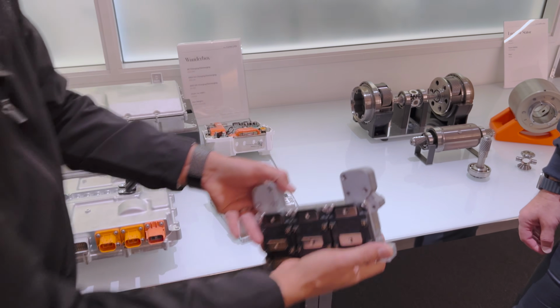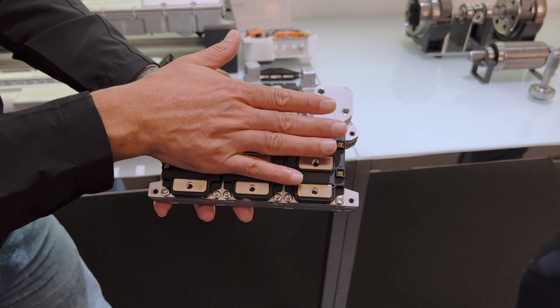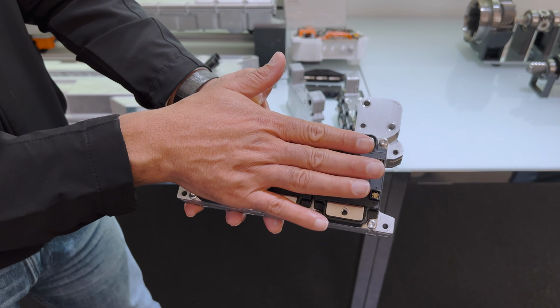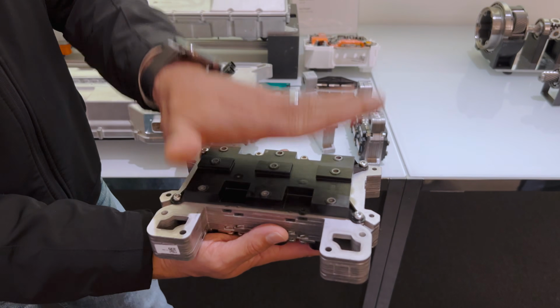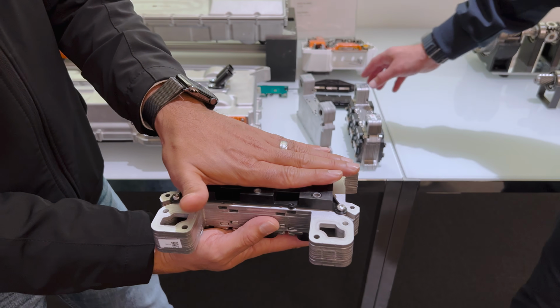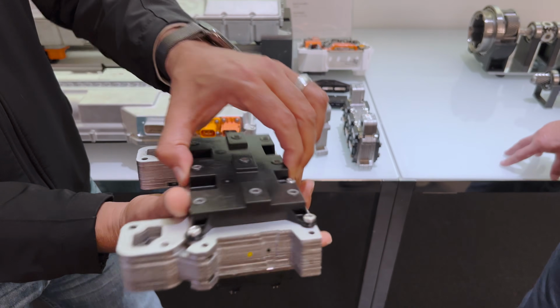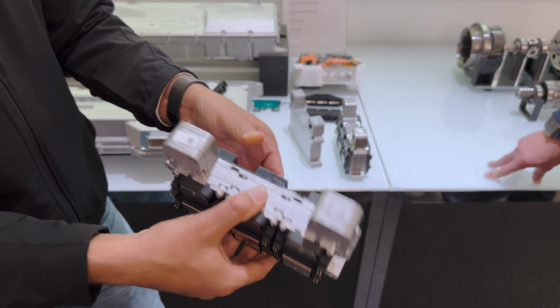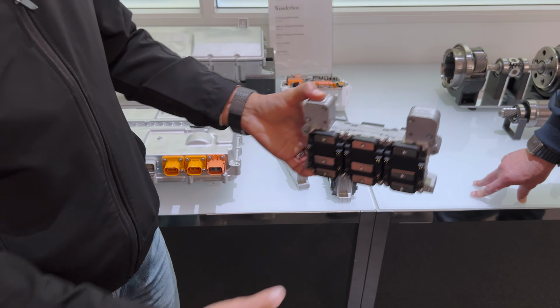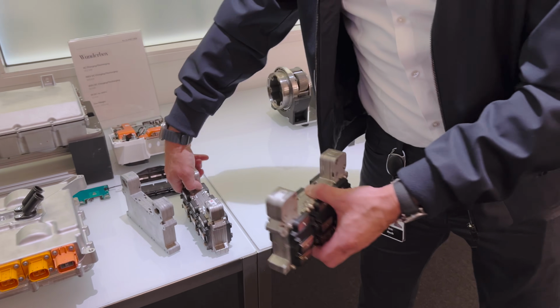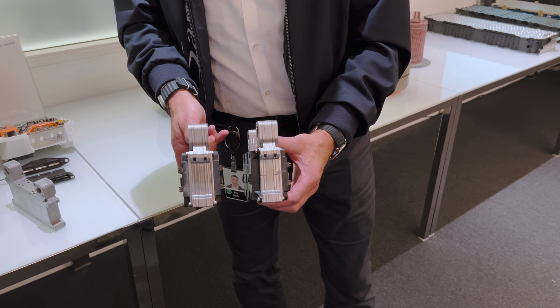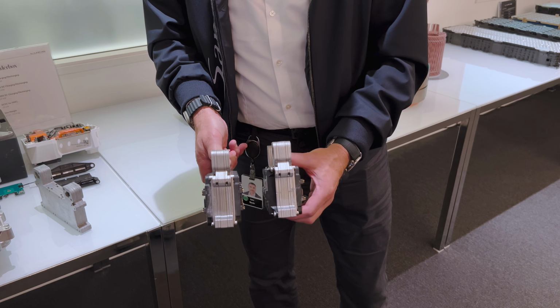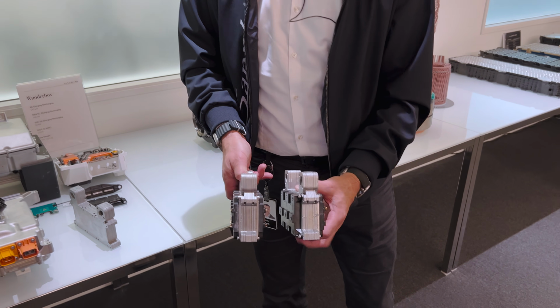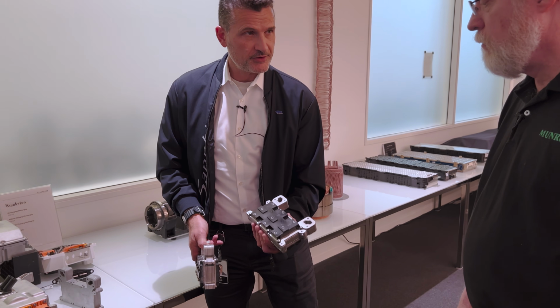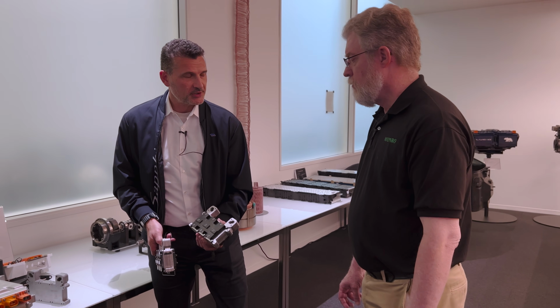As mentioned earlier, we have 2 inverters. This is half inverter, still a full inverter but half power system, 250 kilowatt. Adding these would make 500 kilowatt, but in this case it's just a dummy object here, from a packaging point of view, to keep it symmetric. So it shows we have 2 versions using very similar components, meaning we can build variations simply, doubling the volume on the heatsink without adding cost to the lower power version. It's very modular technology.